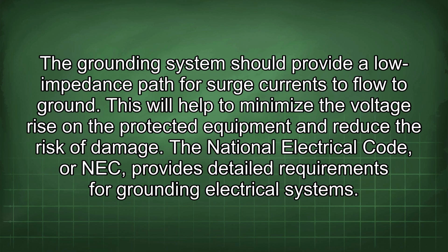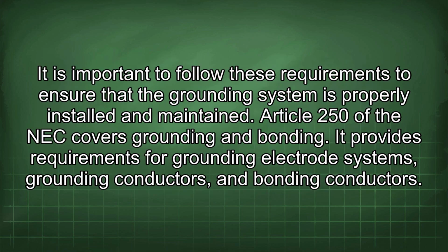This will help to minimize the voltage rise in the protected equipment and reduce the risk of damage. The National Electrical Code, or NEC, provides detailed requirements for grounding electrical systems. It is important to follow these requirements to ensure that the grounding system is properly installed and maintained. Article 250 of the NEC covers grounding and bonding.